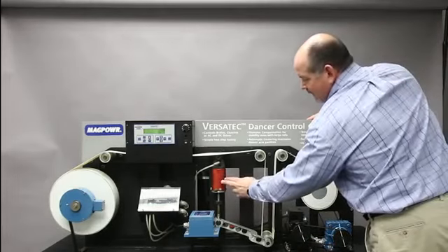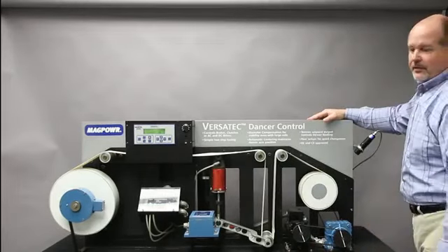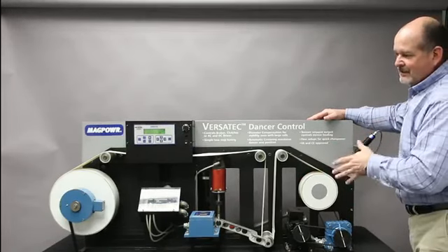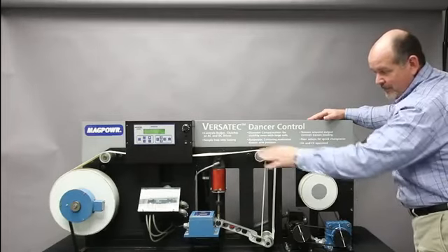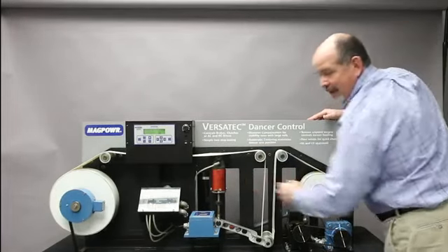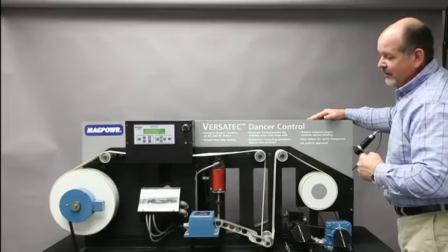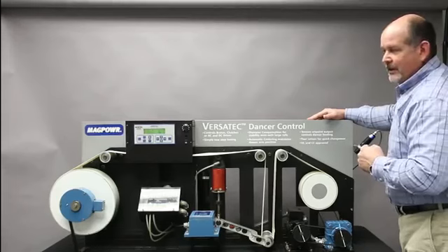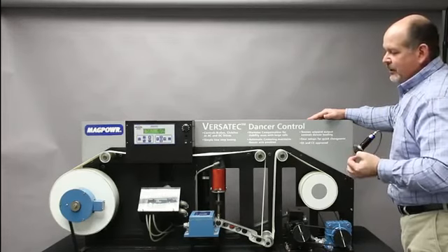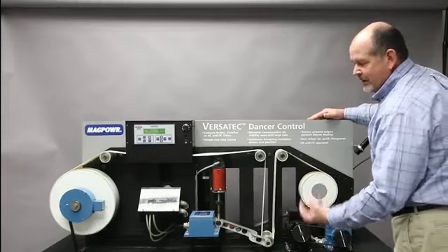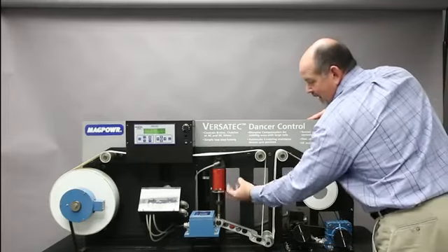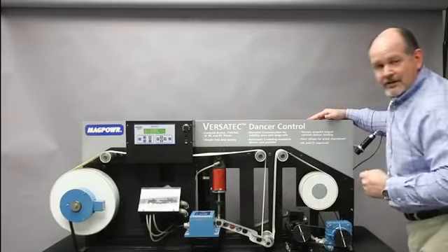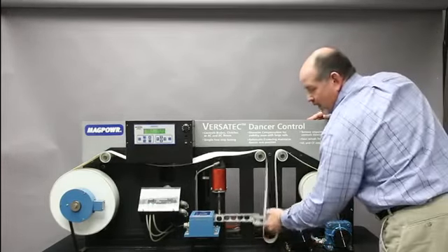The next item that we have here is the actual air cylinder that's loading the arm. Remember I said earlier that in this case the tension is not being set by the torque device, the clutch or the brake. It's actually being set by the air or the load that's in this cylinder. Now this cylinder is a rolling diaphragm cylinder. We always recommend using low friction type cylinders. In the case of a rolling diaphragm cylinder, instead of having a piston and O-rings, what we have is actually a diaphragm or a bladder that's inside of there, and there are actually linear bearings on that shaft, so it's very smooth when it goes up and down.